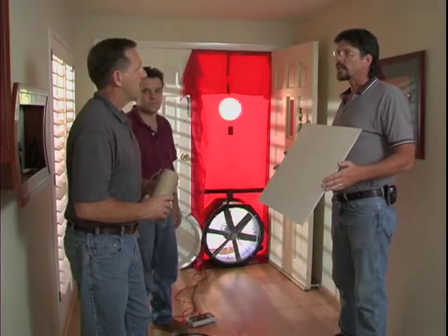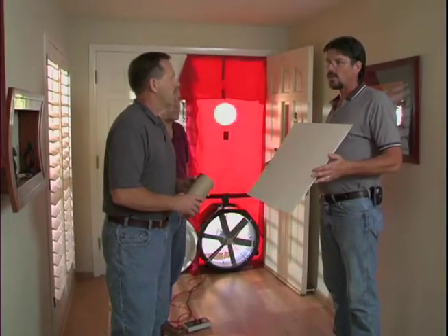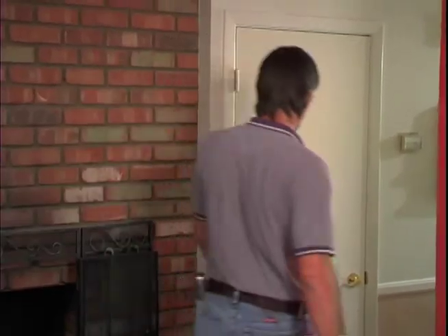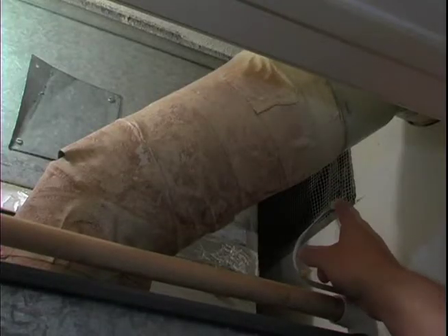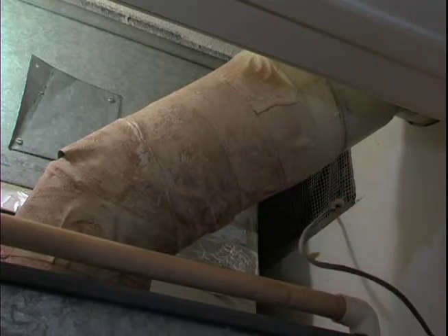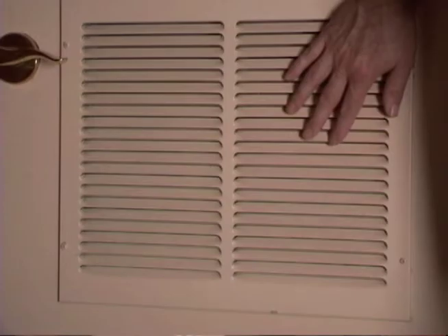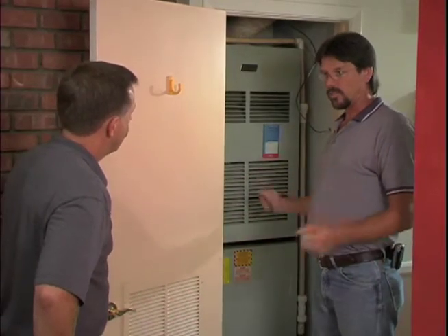Earlier today, Charlie and I took a tour of the home to look for the standard culprits that are in a home of this age, and we found them. Can you show me? You bet. All right, let's go. Okay, well, the first thing that we noticed was the separate combustion vent here, which is supposed to be connected to the outside, is also connected to the attic. And we also have this vent here in the door, which is connected to the inside. So this is a really big hole.